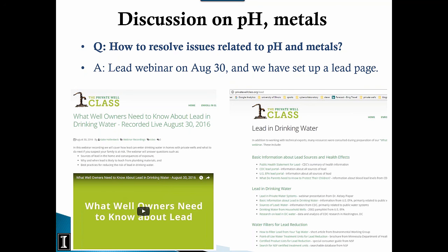I recommend going there, and if you have questions after that, you should contact us, because it's a huge issue. In a lot of cases, there's nothing to worry about. If your water's not corrosive, it doesn't matter if you have lead pipes or not, right? They form scale. Water either causes corrosion or it causes scale to form. On a lot of natural groundwaters that aren't corrosive, these lead pipes have a scale layer built up on the inside of them over time, and it doesn't matter what materials they're made of. So it's only if there's a change or if your water's corrosive that you need to worry about some of those issues.